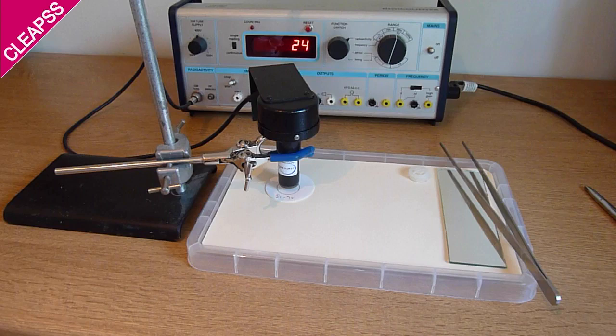If you have radium sealed sources, do them last, because they can show contamination from the outgassing of radon, and this technique minimises the risk of cross-contamination.